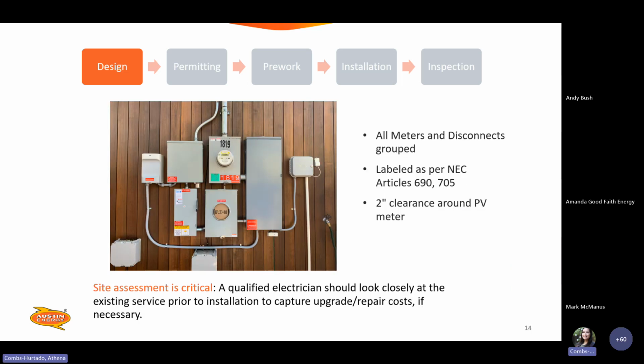Okay. So in the design phase, make sure that you're doing a site assessment and look closely at the existing service before installation to capture any upgrades or repair costs if necessary. All meters and disconnects are grouped, labeled as per NEC 690 and 705, and then 2-inch clearance around the PV meter.